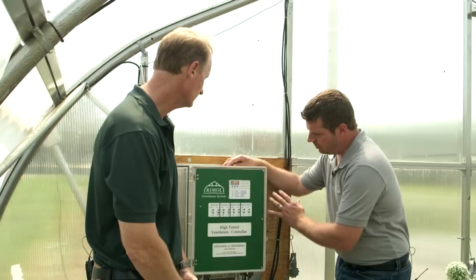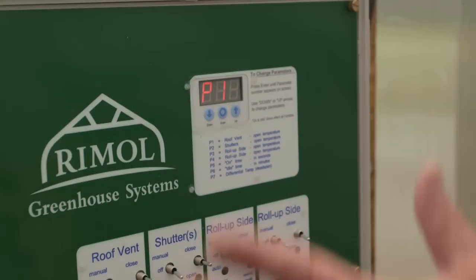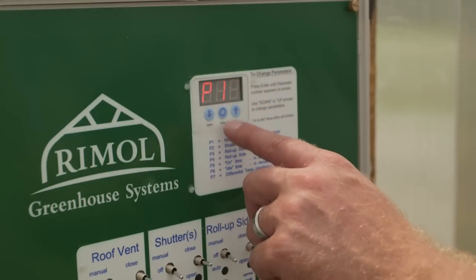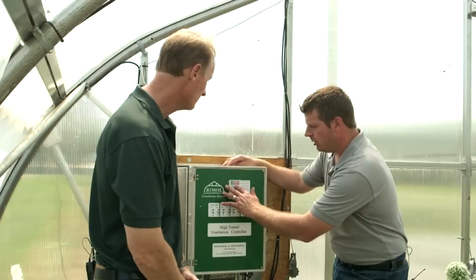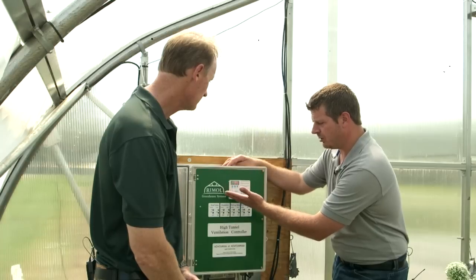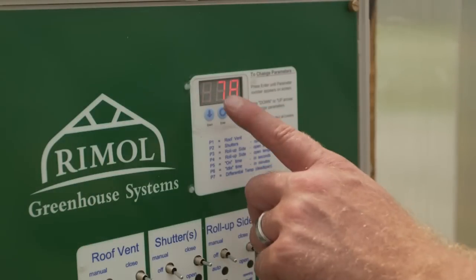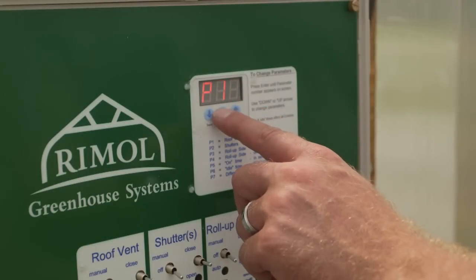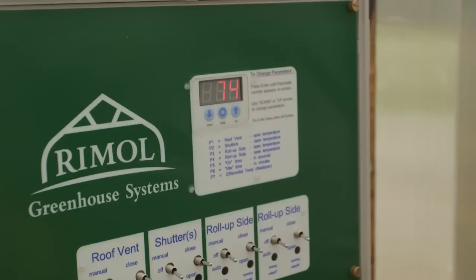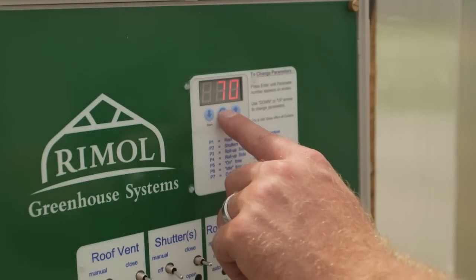As far as setting these parameters, it's a very easy thing to do. There's an enter button and that takes you to parameter one, which is your roof vent. Currently we don't have a roof vent on here, but typically you would set that temperature to where you want that to open. Then you just hit enter again and it'll take you to your shutters and tell you where your shutters will open. For this one we have it set at 78 — we're just going to bump that down to 70 — and then we're going to hit enter.